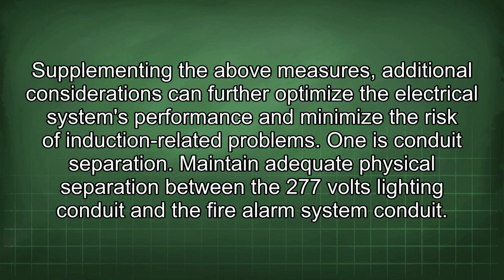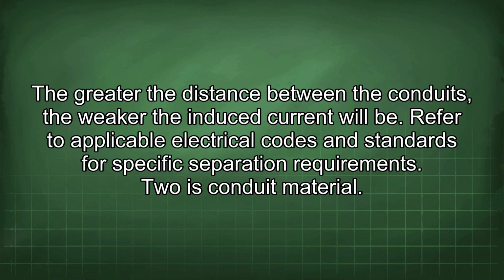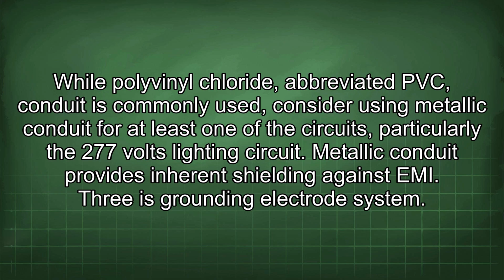One is conduit separation. Maintain adequate physical separation between the 277 volts lighting conduit and the fire alarm system conduit. The greater the distance between the conduits, the weaker the induced current will be. Refer to applicable electrical codes and standards for specific separation requirements. Two is conduit material. While polyvinyl chloride, abbreviated PVC, conduit is commonly used, consider using metallic conduit for at least one of the circuits, particularly the 277 volts lighting circuit. Metallic conduit provides inherent shielding against EMI.